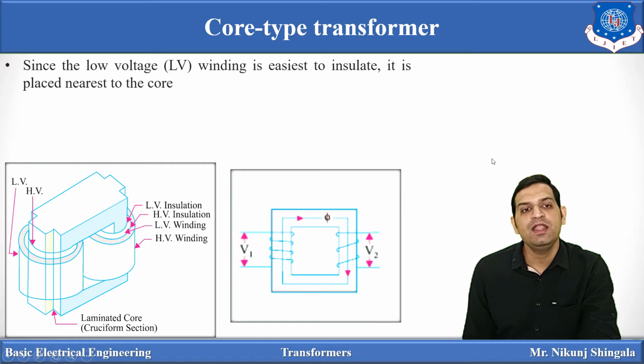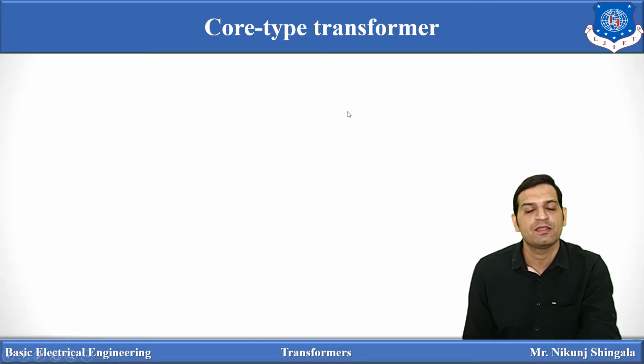Now, low voltage winding: here you can see there are layers of the windings. The low voltage winding is placed nearer to the core because it is easy to insulate. The high voltage winding is placed over the low voltage winding because it is required. High voltage winding requires high insulation, and if we provide the high insulation near the core, it ultimately increases the cost of the transformer. If the high voltage winding is not provided high insulation, it will damage the core. That's why the low voltage winding is placed first, then the high voltage winding, then again the low voltage winding, then again the high voltage winding.